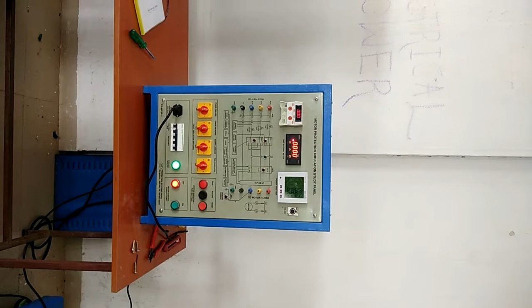Whenever the current is 300%, that is, when the motor current is 1 ampere, if the current going through the motor is above 3 to 3.5 ampere, then the rotor and the stator will be in a lock position. The rotor will not rotate. So that is called lock condition. Stall and lock are almost the same. If the motor current is more than 200%, it is called stall. If it is more than 300%, it is called lock. You can observe it here, sir.